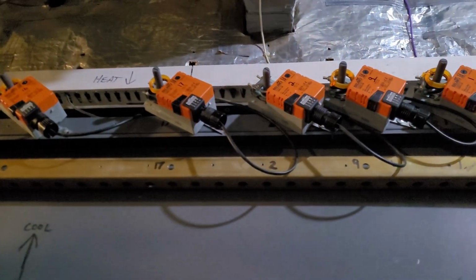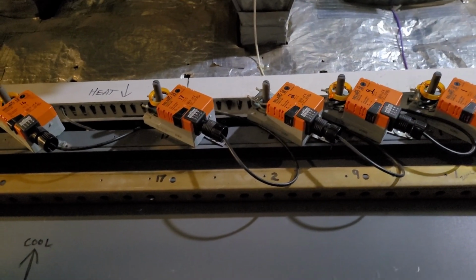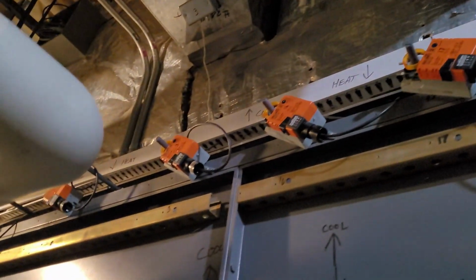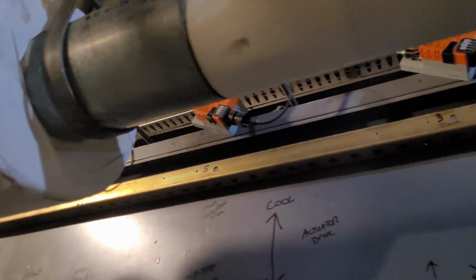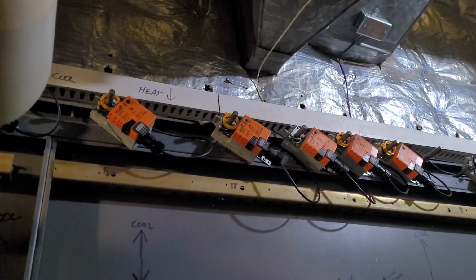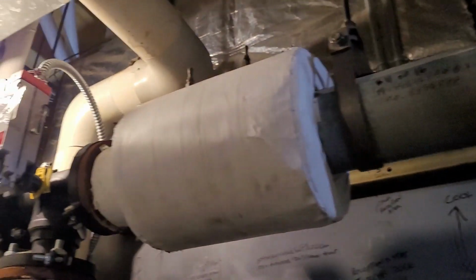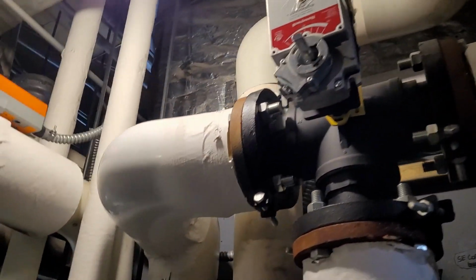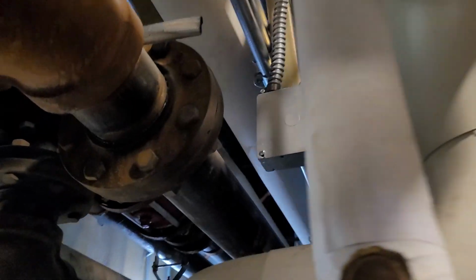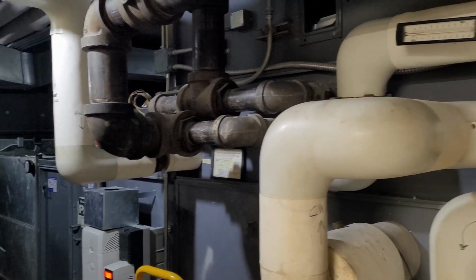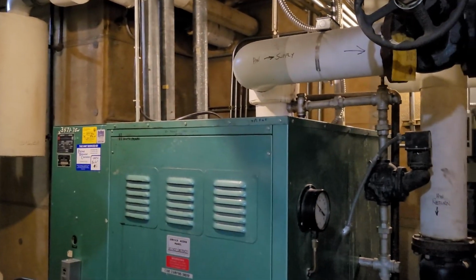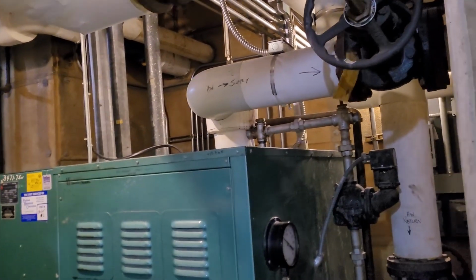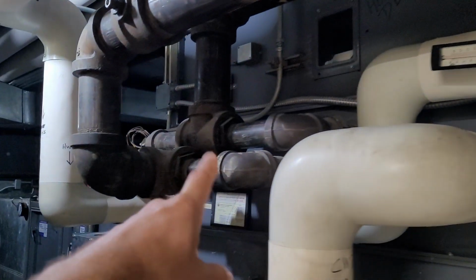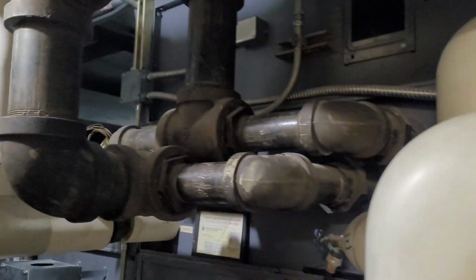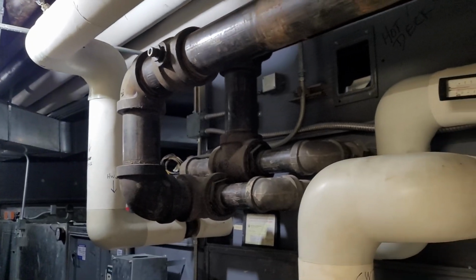Any one of those dampers can choose either hot deck or cold deck. So you could have heating in one zone and cooling in another zone. You could cool one zone and take that heat and move it over to the hot deck and use it to heat a different zone. That way you don't have to run your boiler at the same time that you're running your chiller. You can take that condenser water, and if you need just a little bit of heating, you can get it there. I don't think I've ever seen that in Texas. So here in Washington State, they had a good idea, a little bit of heat recovery.